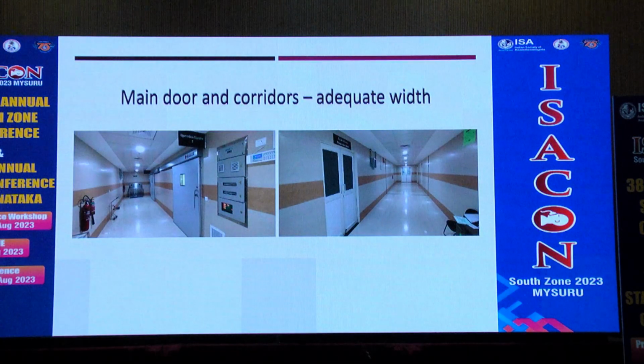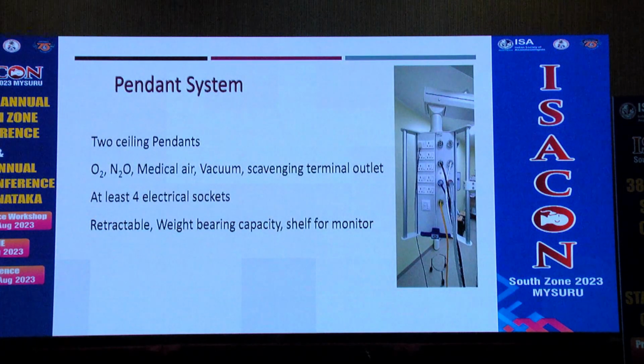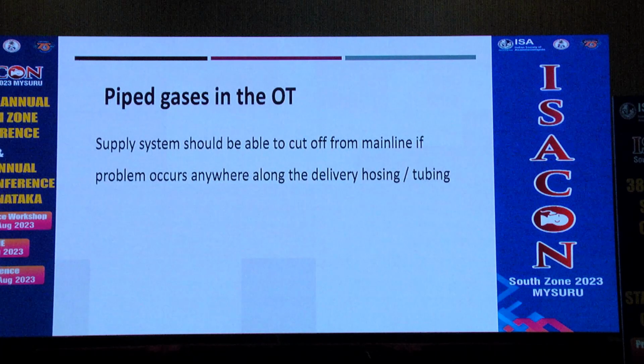The main doors and corridors should be of adequate width to allow the passage of a patient trolley. For the pendant system, there should be 2 ceiling pendants, one for anesthesia and one for surgery. Our pendant system should have 2 oxygen, nitrous, medical air, 2 vacuum and at least 1 scavenging terminal outlet, 4 electrical sockets, and should be retractable, with a shelf for the monitor. The piped gas in the OT should be able to be cut off from the main supply if any problem occurs.